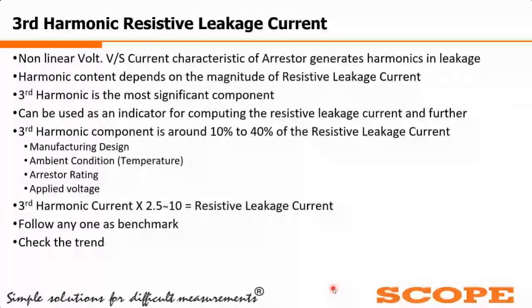Now what we know as a standard thing is that the third harmonic is the most significant component out of all the harmonics, and hence we can use the third harmonic as an indicator for computing the resistive leakage current and for further analysis. Now this third harmonic component, as IEC or other researchers have found, remains in between 10 to 40% of the resistive leakage current.